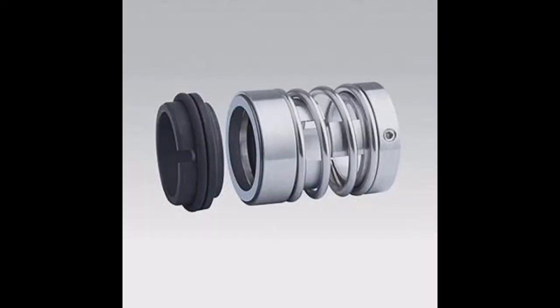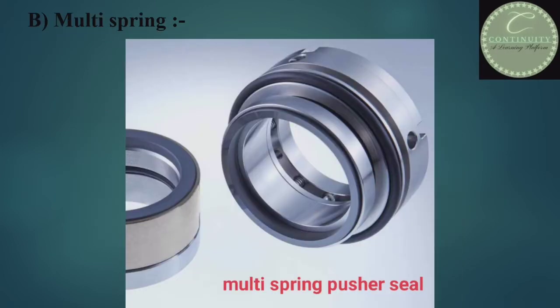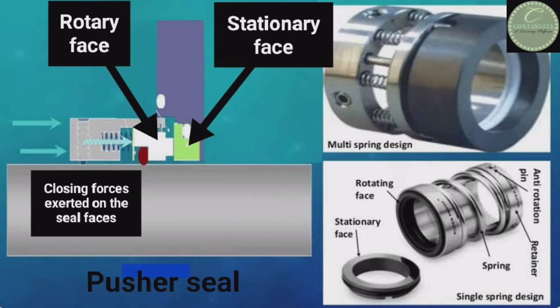A pusher seal is basically installed with a single spring or multiple springs, as well as a movable O-ring which acts as a secondary seal. The spring is used to maintain contact between the seal faces, and the O-ring is used to prevent leakage between the sleeve and the rotary unit. It moves on the sleeve or shaft with the help of the spring to maintain contact between the rotary seal face and stationary seal face, with closing force applied by the springs.